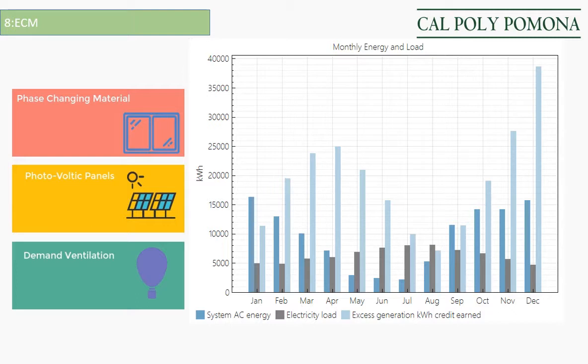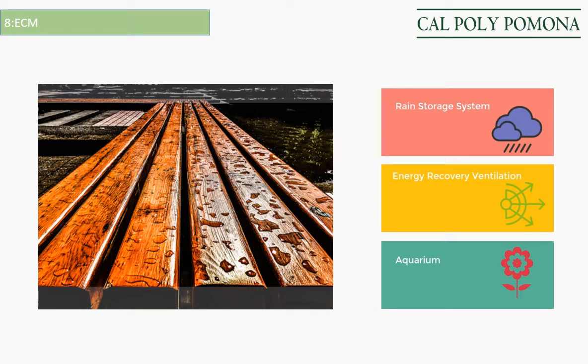The ventilation load accounts for the largest heat load. By adding CO2 occupancy sensors to the spaces, minimum ventilation requirements for people drop significantly. The rainwater storage system was analyzed per owner's request. More than 600,000 gallons of water can be harvested per year with the 43 inches of annual rain and 19,000 square foot roof. Only a 6,000 gallon storage tank is needed to offset the water consumed by the radiant floor heating system with VAV bypass.